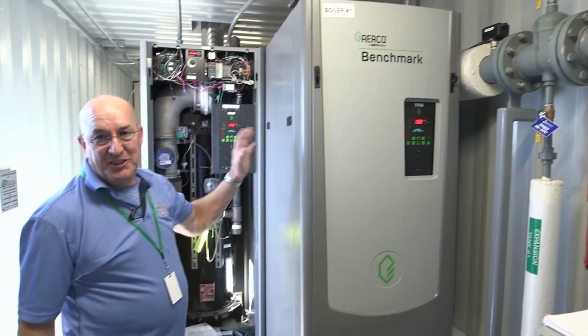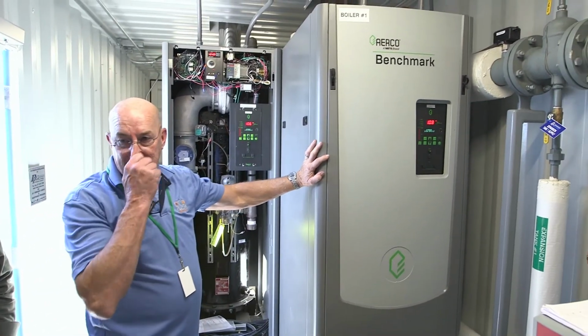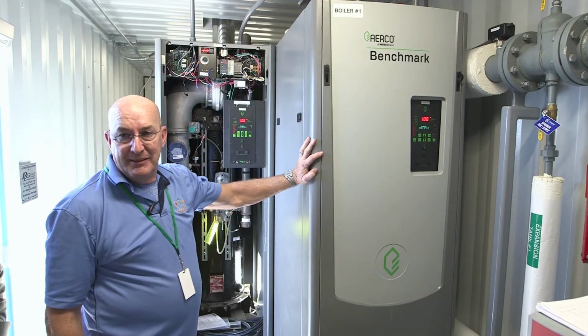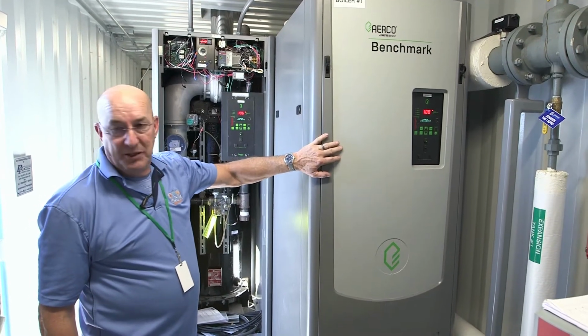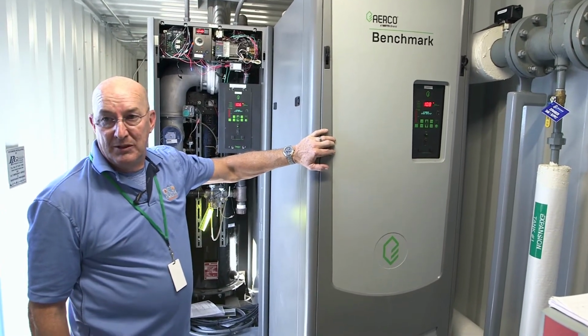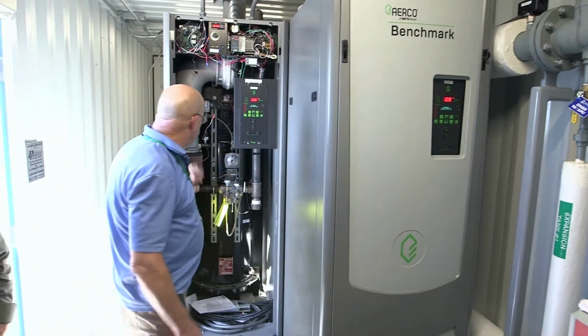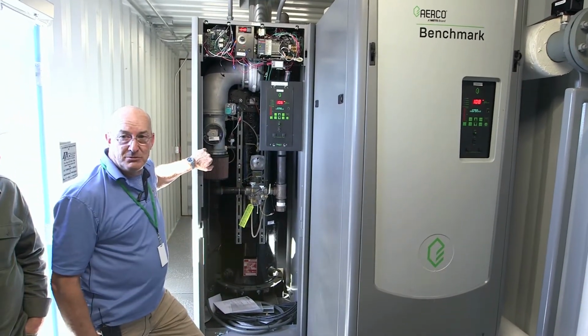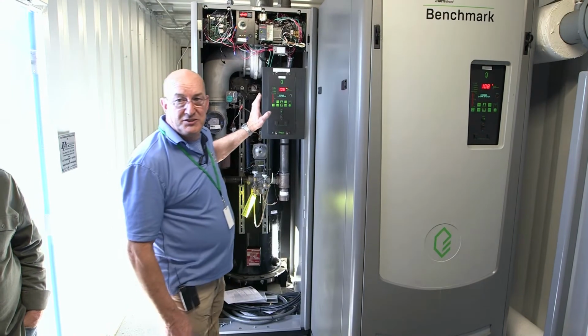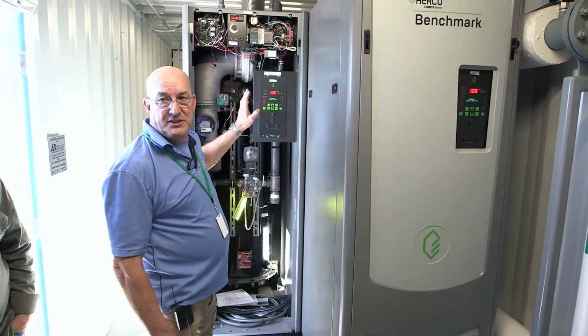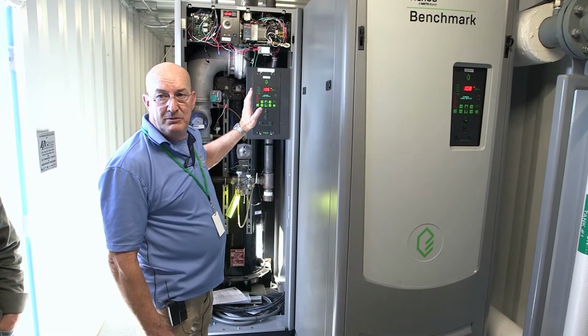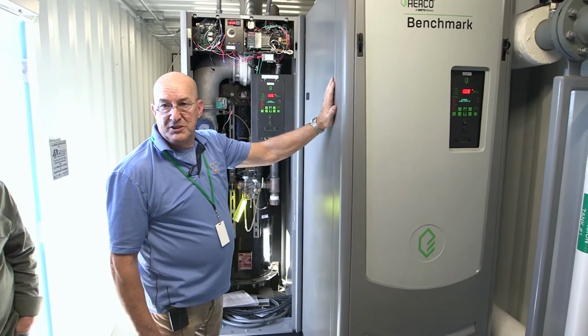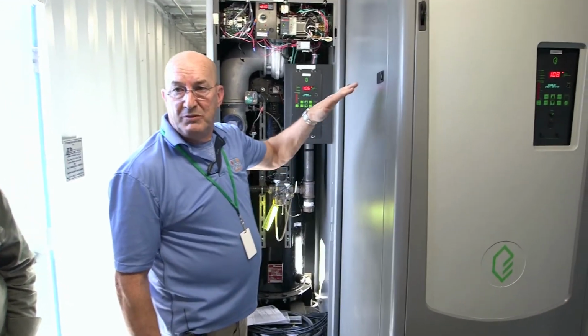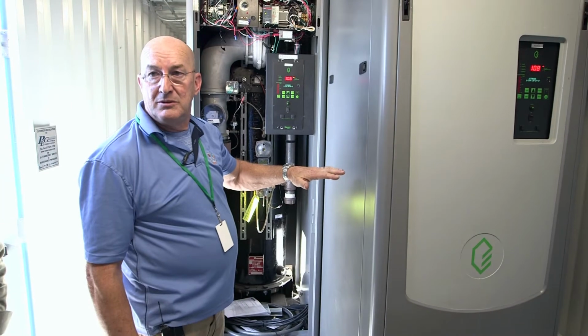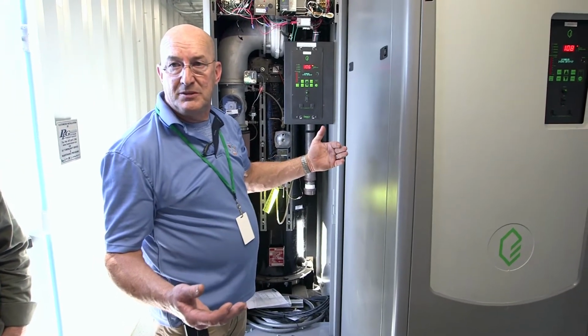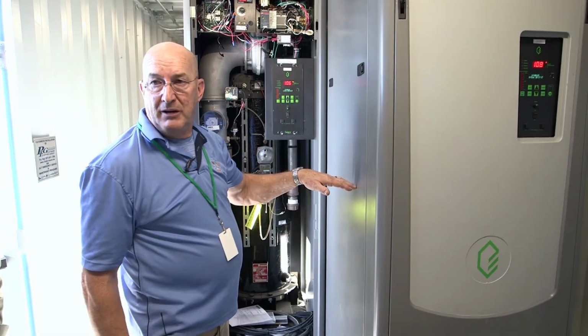As you can see, you have 2 boilers here. They run lead lag. This is boiler number 2, or the slave boiler. This boiler will not run unless this boiler gives it a signal to run. This boiler decides according to temperature. It says, listen, I can't keep up with the load. It transfers over to this one, brings it up to whatever percentage it needs to bring the temperature up fast. It'll also ramp down.